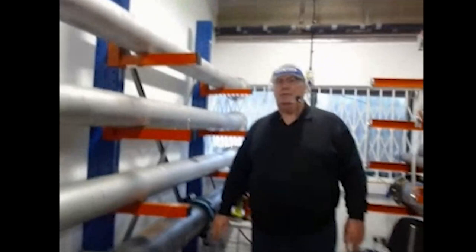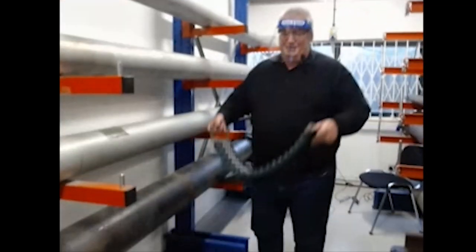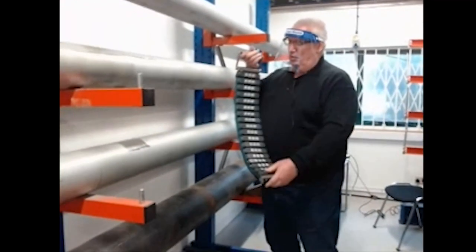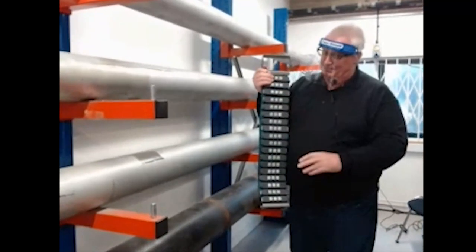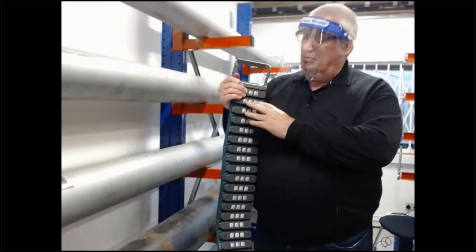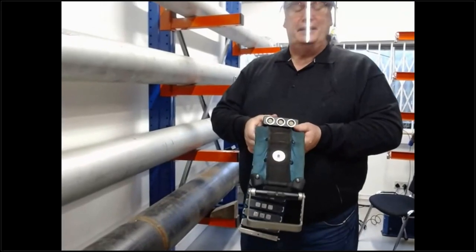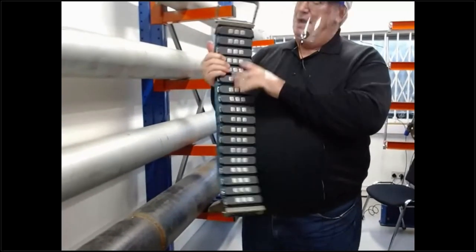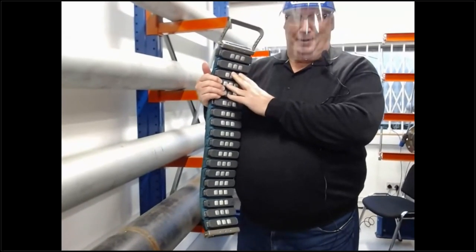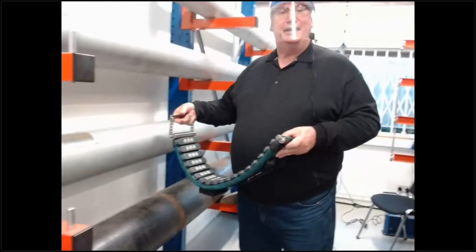Back onto the compact ring — this is the new latest version. Lightweight, which I'm glad for because I'm obviously trying to handle it. You'll find there are low profile probes in it. Different to the conventional rings, these have three probes instead of two. What this enables you to do is change frequencies by just putting data cables in different positions, rather than manually changing the distance between the probes. So that saves time doing each module. As you can see, it requires less clearance around the spool piece. So I'm now going to attach it to the 6-inch.